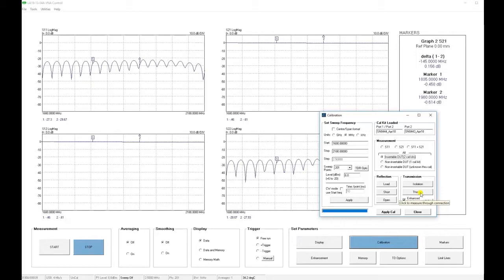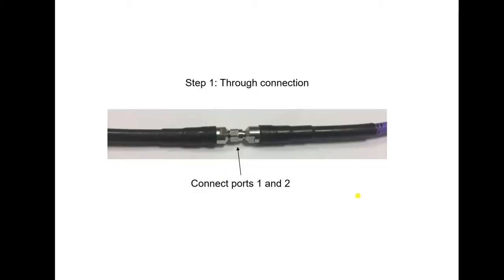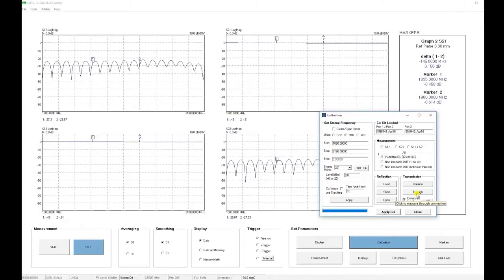That is where we simply connect the ends of the test cables together as shown. We can make the through measurement at a relatively high bandwidth of 1 kHz. We click on the through button, click OK, and the measurement is made.